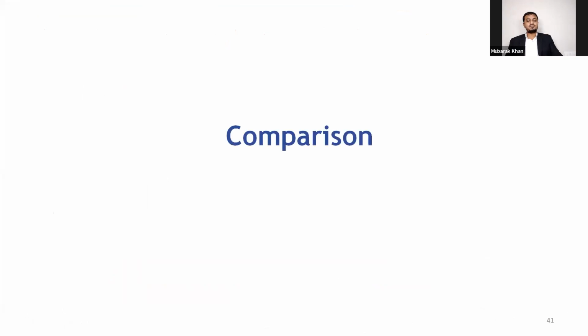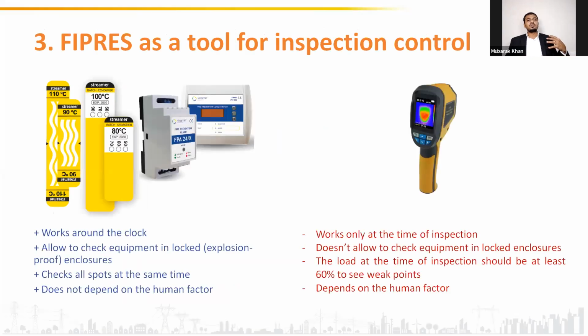Let us compare. Normally, the technology we use for monitoring electrical joints is thermal imaging. Let us compare with thermal imaging, and we'll do a detailed comparison later also. Thermal imaging works only at the time of inspection and doesn't allow checking equipment in locked enclosures. The load at the time of inspection should be at least 60% to see the weak points, and it highly depends on the human factor.